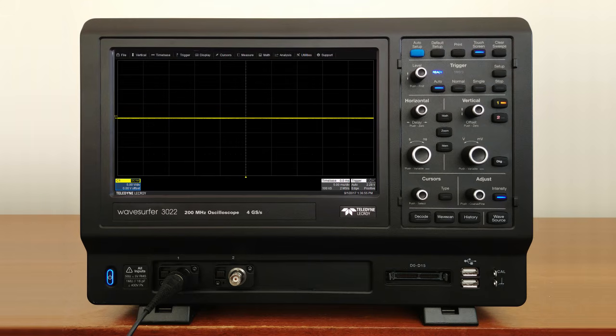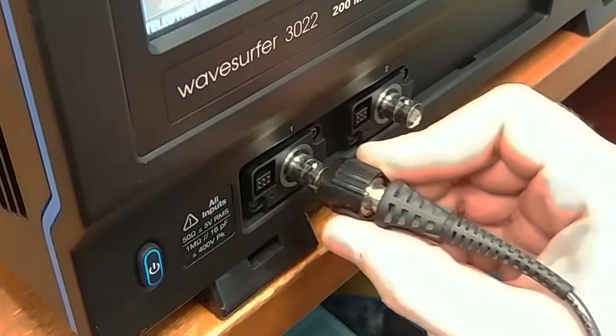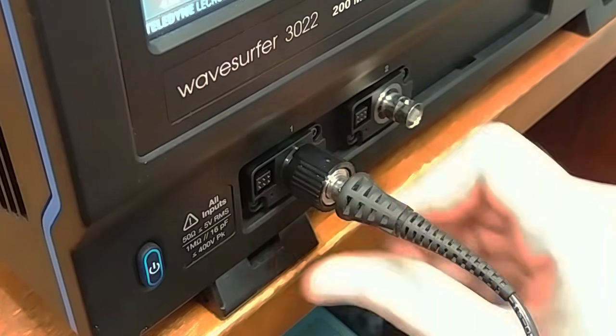Oscilloscopes measure voltage. The inputs are along the bottom here. There are almost always at least two channels like on this scope, but some scopes have more, and they're usually called channel 1, channel 2, etc. The inputs use a type of connector called BNC, which allows you to easily connect probes by slipping the connector on and twisting it to lock it in place.